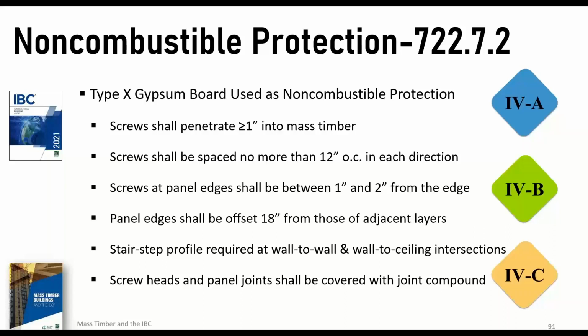But they found out through testing that the type S screws tend to hold a little better. I believe the threads are a little bit finer. They seem to hold the gypsum to the CLT substrate a little bit better. But the very, very detailed fastener schedules, very, very detailed lapping requirements, abutting joints, edges, and we already talked about the lapping of the corners in the wall and ceiling assemblies when we're doing this non-combustible gypsum protection.